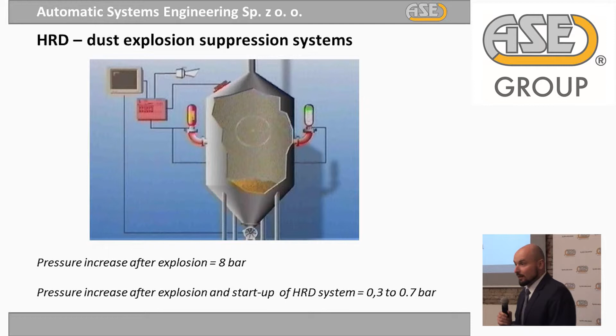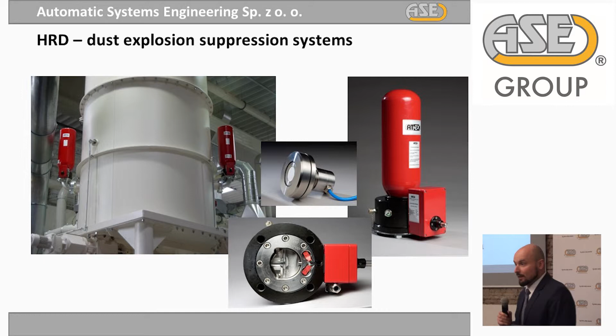Dust explosion suppression systems for dust ATEX zones. It's a special technology with very fast opening valves, reacting in less than 1 millisecond, then opening the valve within the next millisecond. In under 2 milliseconds together, the bottle opens and special powder inside, under 80 bars of pressure, fills the installation and stops the explosion before the pressure can rise. The energy of the explosion is decreased 10 times, making the installation safe. We just need to clean the white powder afterward, and the installation keeps working for years.